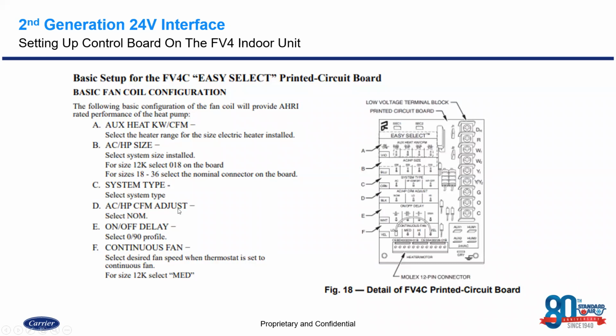Our AC heat pump CFM adjust, you can see here it says select nominal on there. Nominal is just to receive the AHRI ratings that these systems are rated at depending on the combination. You can adjust low or high depending on what the need of the space is. We have our on-off delay on here, which you can see is 090, 3090, or no delay at all.